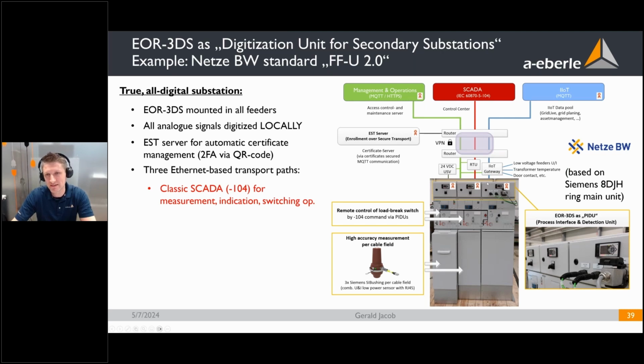So all the devices are connected to the central control center via a classic SCADA protocol, in this case 104, for measurements, for indication, and especially for switching operations. As you can see, there are 2 other protocols in parallel. One of them is the mentioned IIoT, Industrial Internet of Things. Here we don't have a one-to-one connection like in the SCADA protocol path. IoT works a little bit differently. All the data of IoT are sent to a central broker, and a lot of different users can then subscribe to this data as they want to. For example, asset management or grid planning can just subscribe to the data they want to use.